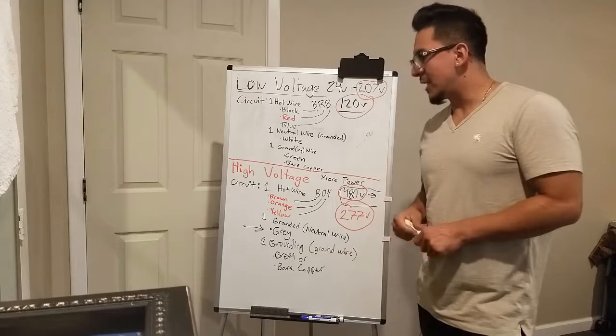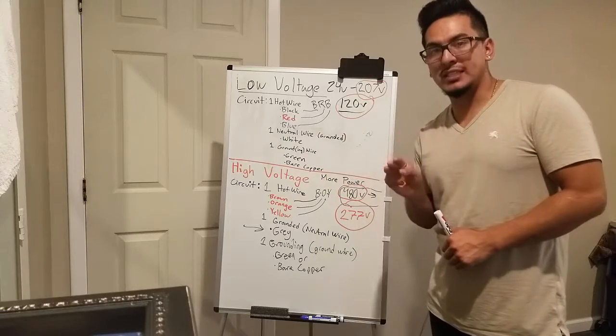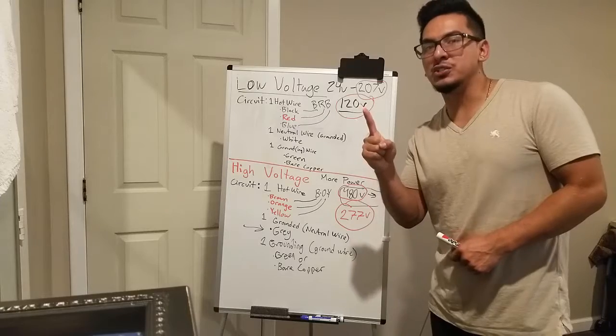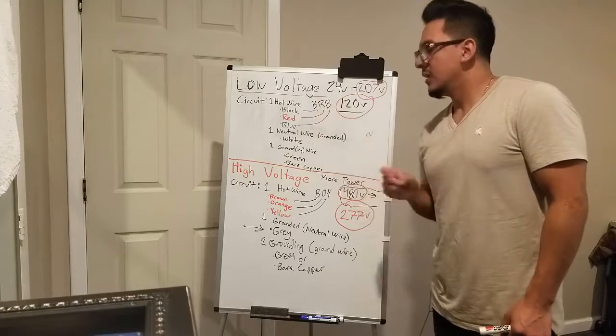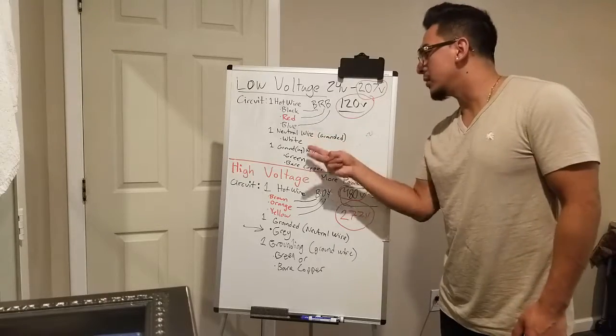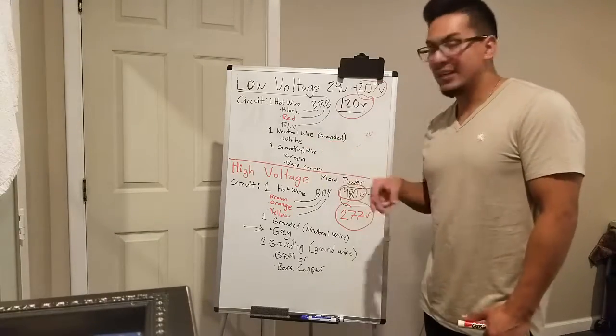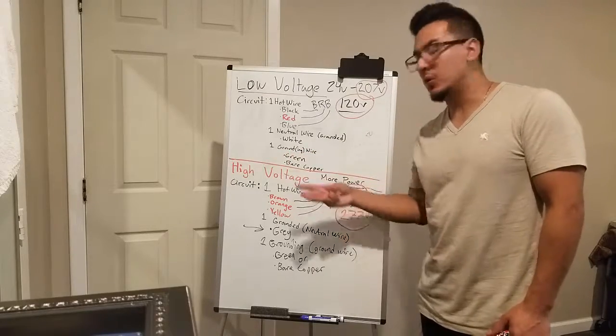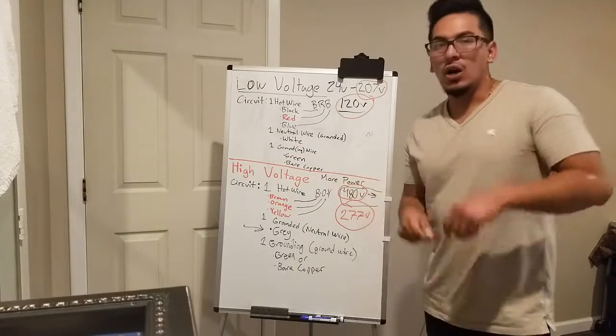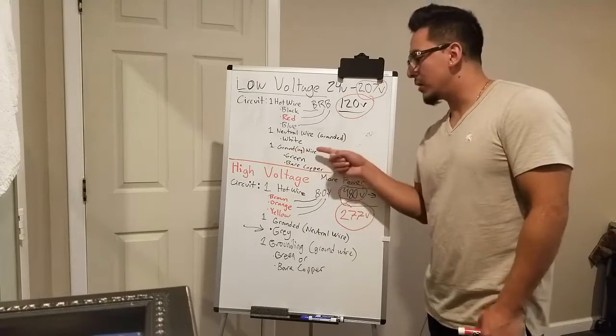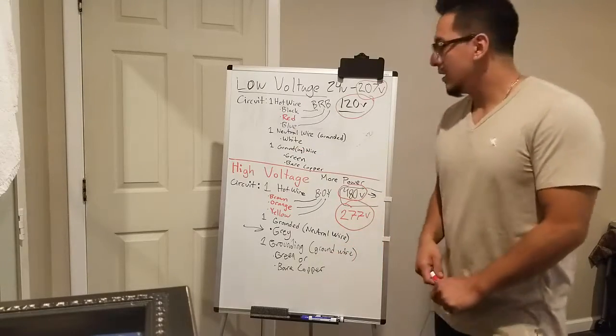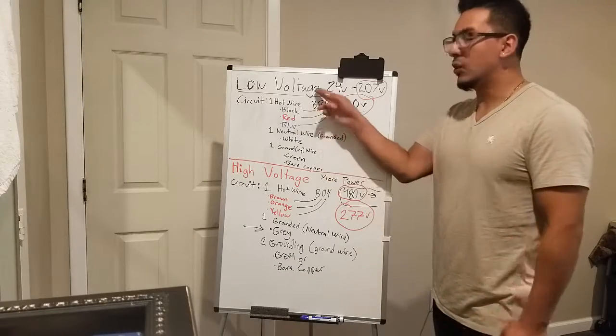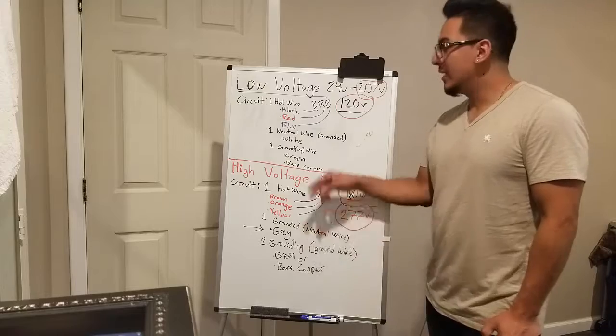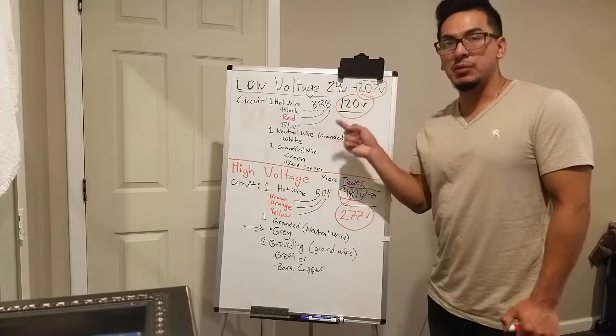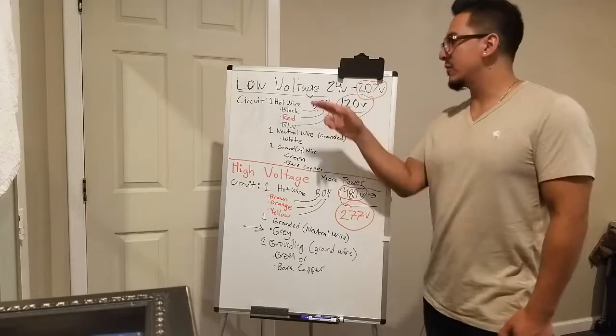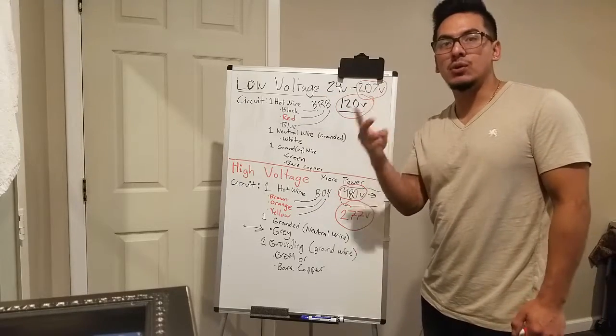The main thing here is you have to learn that a circuit consists of 3 wires: your hot wire, or ungrounded wire, because it's not grounded; your second wire, which is your neutral wire, your grounded wire; and your third wire, which is your ground wire or grounding wire, okay? Always, always, always remember that the ground or grounding wire is green or bare copper. Always remember that your neutral for low voltage is white, for high voltage it's gray, and your hot wires are going to be BRB - black, red, blue, in that order - for low voltage, and BOY - brown, orange, yellow - for high voltage, in that order.